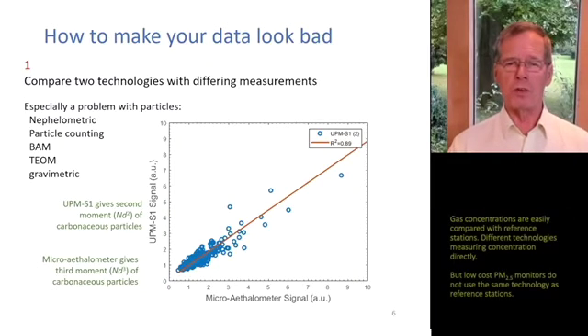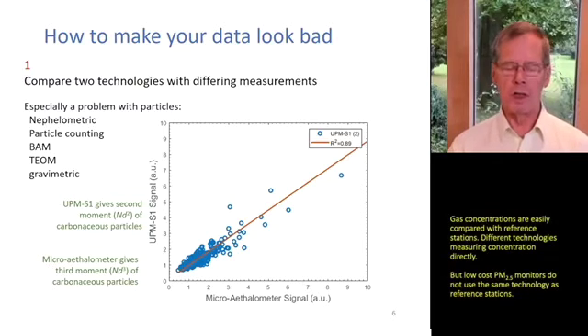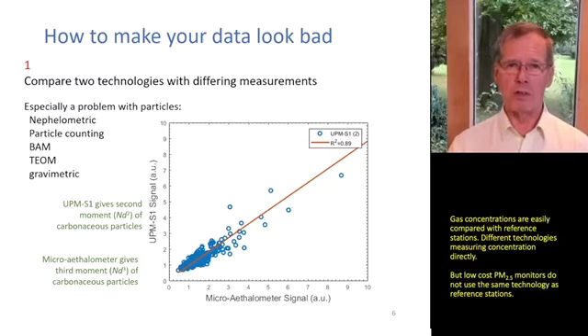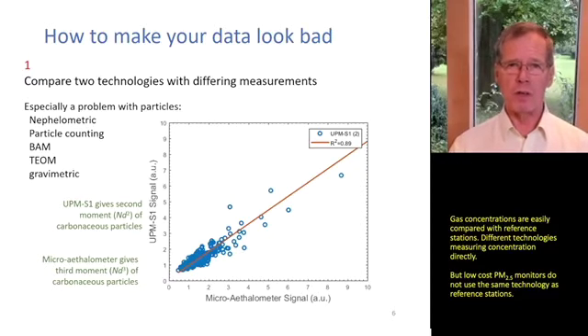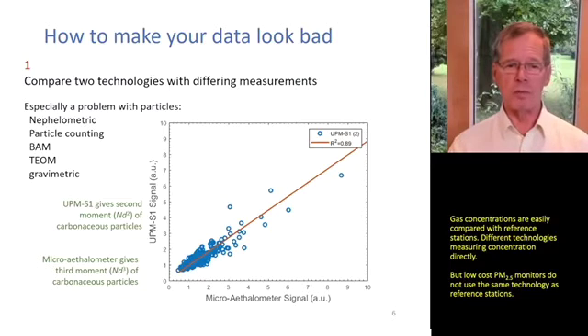The next thing you can do is compare two different technologies — this is especially a problem with particles. When measuring with low-cost particle monitors, you're measuring the integrated scatter by what is called nephelometry. Other technologies include single optical particle counting, beta attenuation, gravimetric, and resonant microbalance measurements. All of these measure different properties of the particles, so when you plot them to get an R-squared, you have to be aware that you're actually comparing two different parameters — and this is sometimes a source of error.